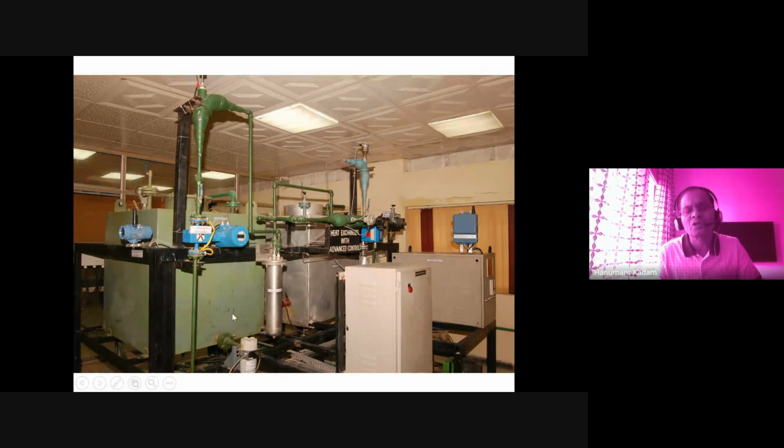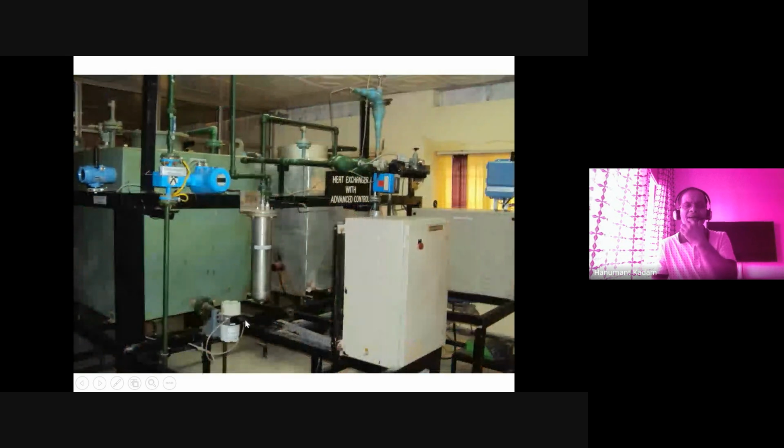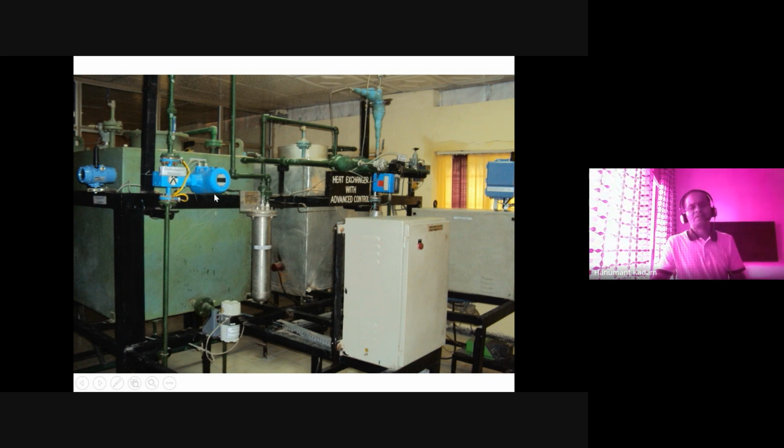You see here, I am talking about this magnetic flow meter, this one. Again, this is more clear. You see the display here. This is the transmitter portion. This can be replaced. This is the actual meter mounted on the pipeline. From here you get the supply. Either the transmitter is embedded or you can have a separate location for transmitters, but in most cases it is embedded, meaning it is on the same body.